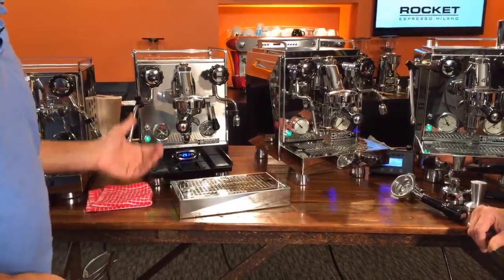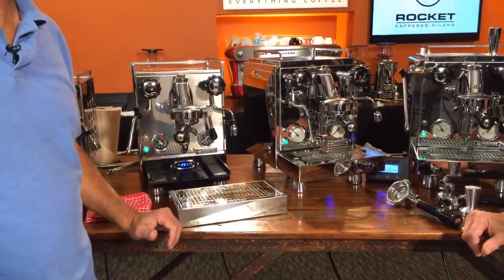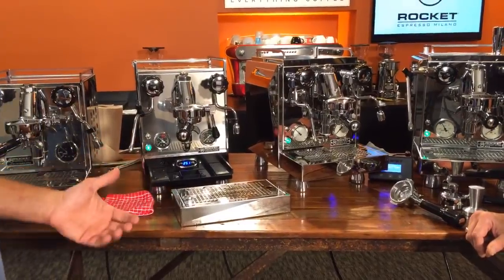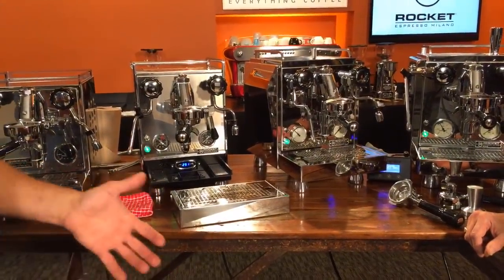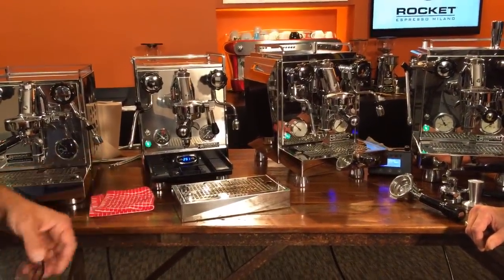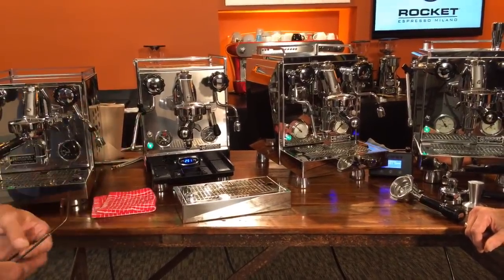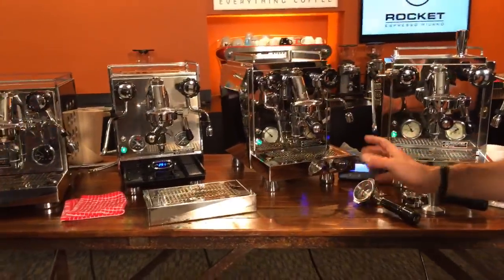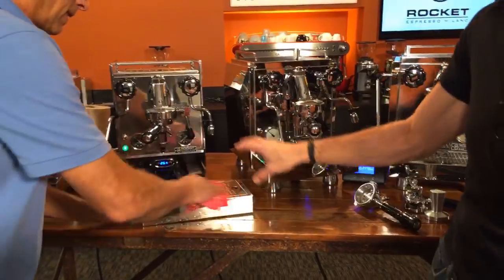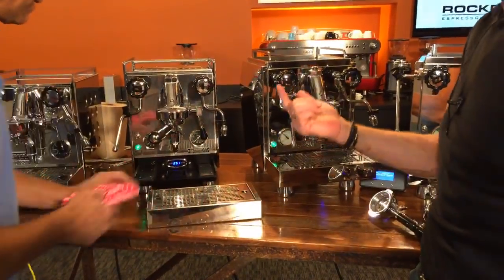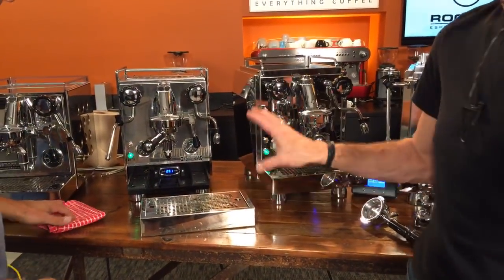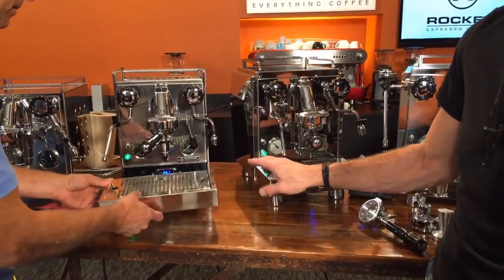Another thing I really like about it is service-wise. These PIDs barely ever go bad. They're very well made, and they have a static relay in there that doesn't arc when it sends power to the boiler. So I really like them, I love the PIDs. But that's about the longevity of the machine. You pay a little bit more for the PID, but you do get a much more stable temperature.